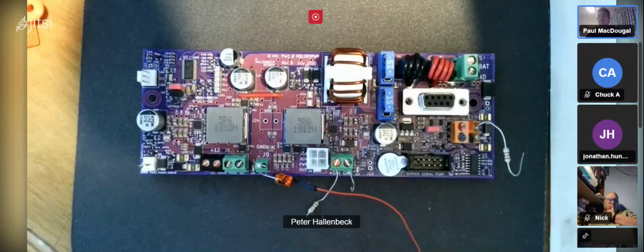Before you pull the power, the serial port lets you pick thresholds for when the voltage is too low and how long after the voltage gets low before you shut off. On the serial port it will tell you how long you have till shutdown. So in Unix land, the task watching the serial port would say, we're going down in 5 minutes, let me warn all the users and then shut everything down.